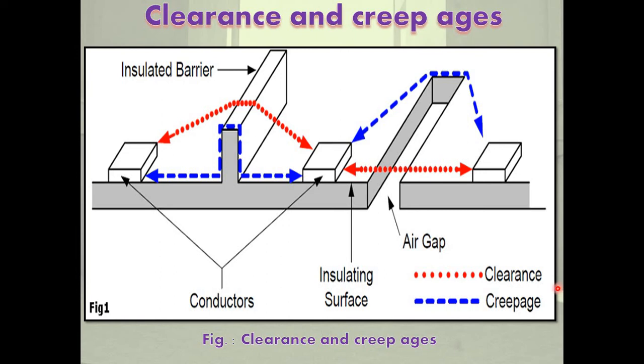Creepage distance is the shortest distance between two metallic parts along the surface of a solid insulator. The surface leakage currents and surface flashover are influenced by this distance. Indian standards, design specifications and safety rules specify certain minimum external creepage distances for equipment with reference to voltage level and degree of atmospheric pollution.